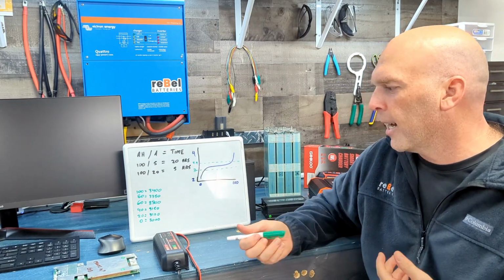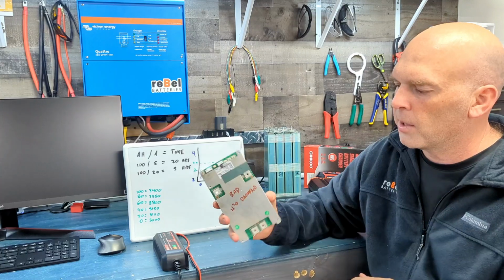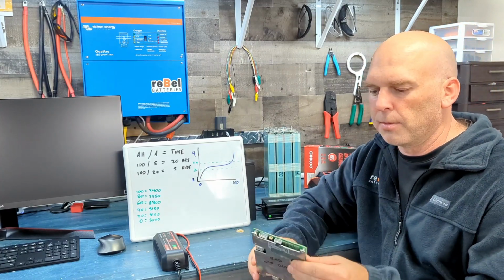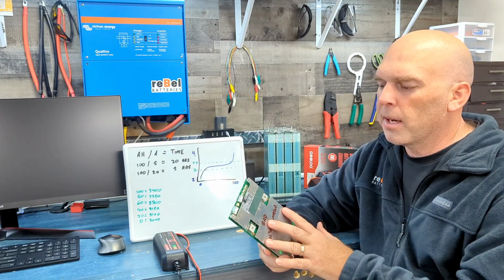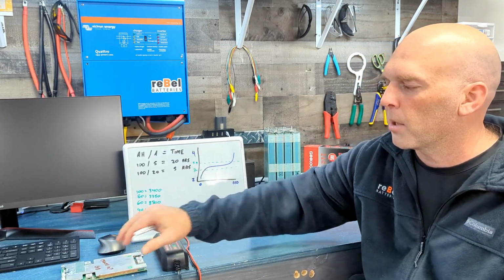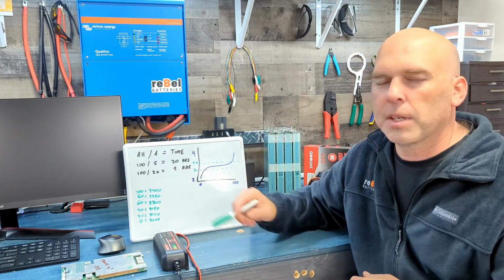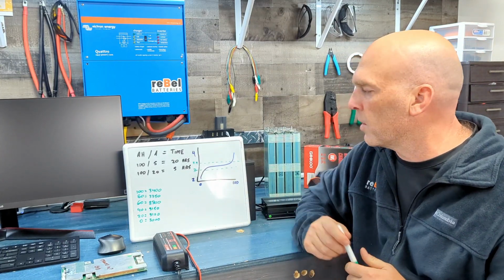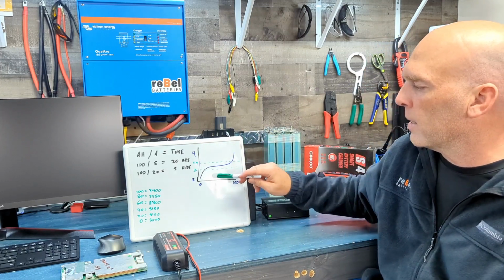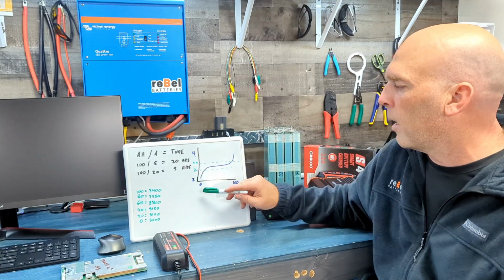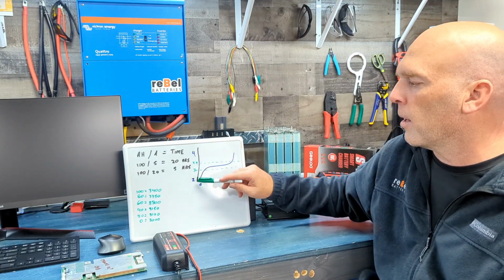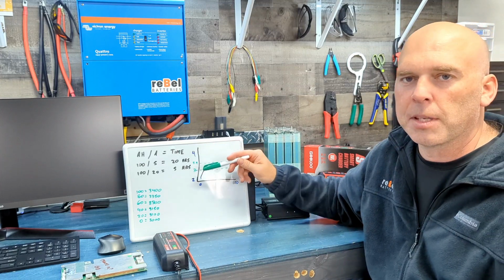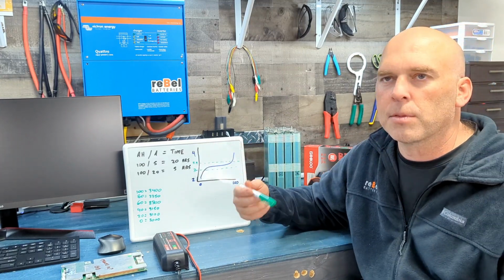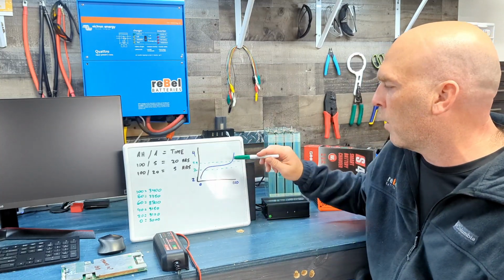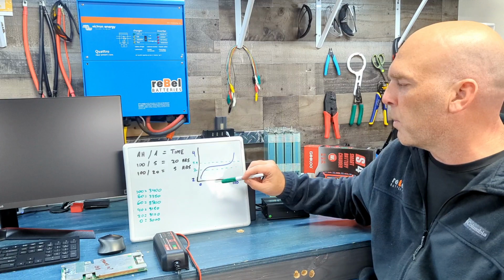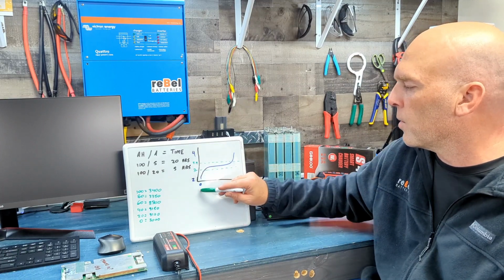Inside the BMS, this one's damaged so I'm just using it as a demonstration and training aid, there's firmware, and inside that firmware there are parameters set, and 100% is set at 3,400 millivolts. This is a charge curve for a lithium iron phosphate battery. You've got 2 volts up to 4 volts, that's the minimum and maximum for a battery. Below 2 volts you'll damage it, above 4 volts you'll start having fire risk and damage issues. So 4 and 2 are the extremes, and the axis here is 0 to 100%.